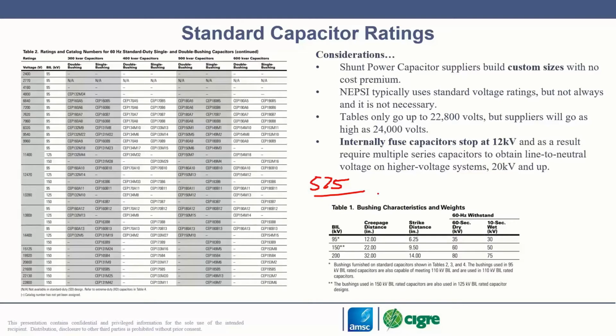We do make a recommendation though in a multi-tune capacitor bank that you design the filter so that it uses the same capacitors throughout. That's a recommendation: come up with designs that utilize the same voltage rating, same kVAR rated capacitors throughout, because it decreases the number of spare components required on site.